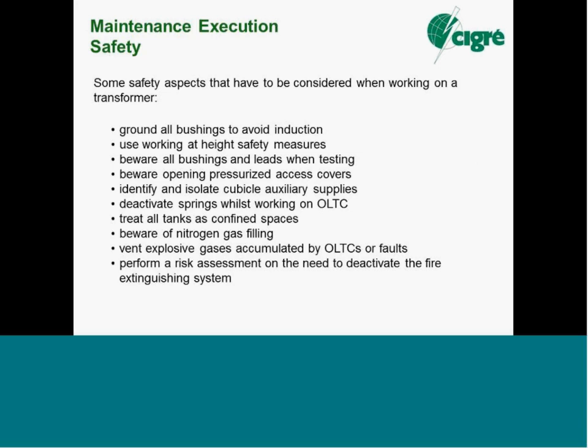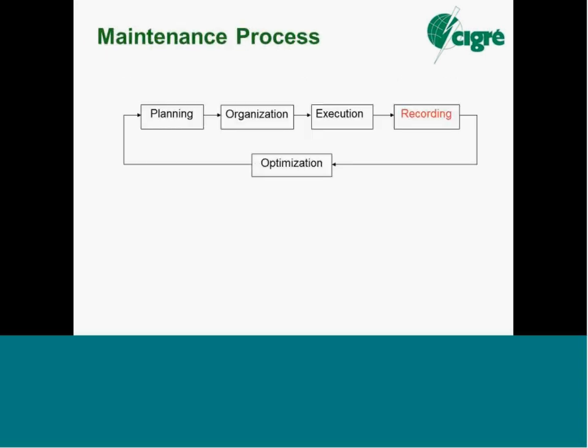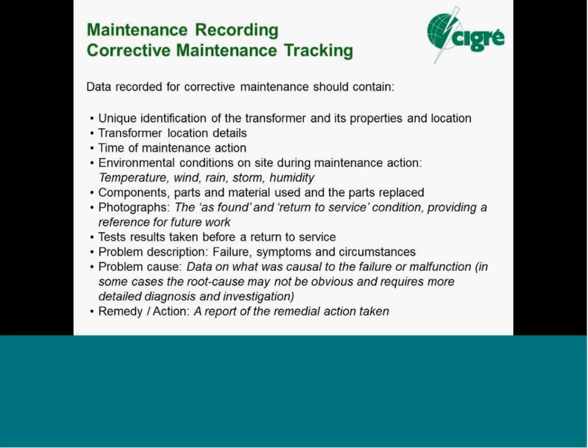In execution, we make some interesting comments on both the safety of people but also the safety for the transformer. Reading that, and in maintenance records, so often I see electrical tests done or oil samples taken on the transformer and not enough information recorded. The conditions of the day, was it raining, what was the ambient temperature, what was the operating temperature of the transformer in the case of an oil sample being taken, what was the load on the transformer. For electrical tests, the temperature of the transformer insulation, granted it's offline, has cooled down, but still, depending on ambient, and if the transformer is still cooling down, the temperature of the insulation affects the result of the test.